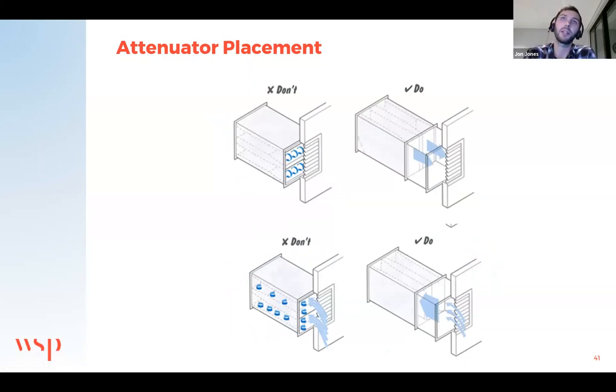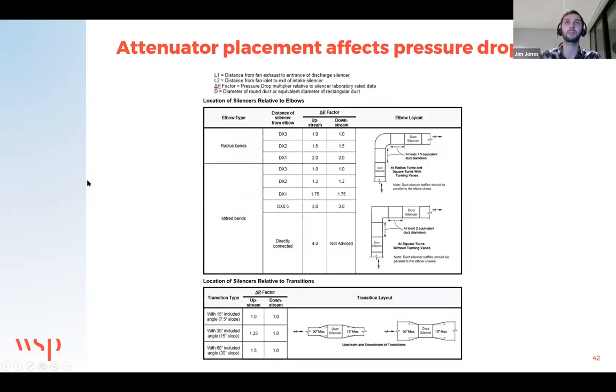It's not just attenuators, but same thing with grills, essentially. It's always good to have a plenum space between attenuators and grills, diffusers, basically for the same reasons as we touched on with the attenuators. There's a bit of data there. There are correction factors we can apply. Ideally these things would be avoided for optimal performance and minimum resistance to the system, but if we know what the setup is, we can look at it and consider what the impact might be, and it can be factored in again with fan selection and suitable power for the fan.